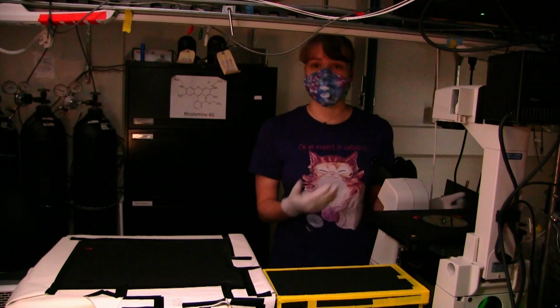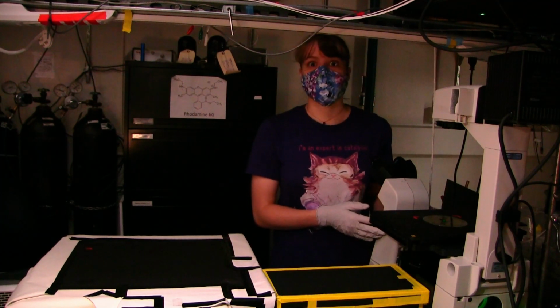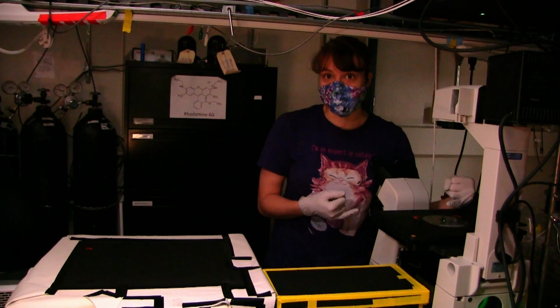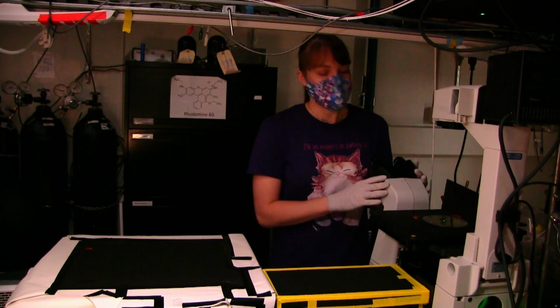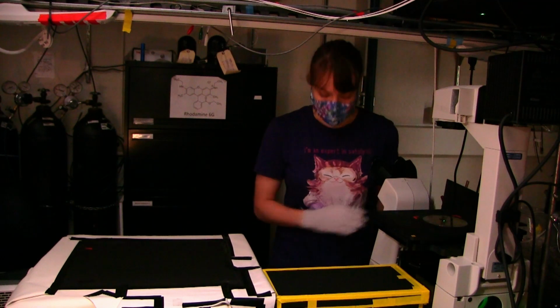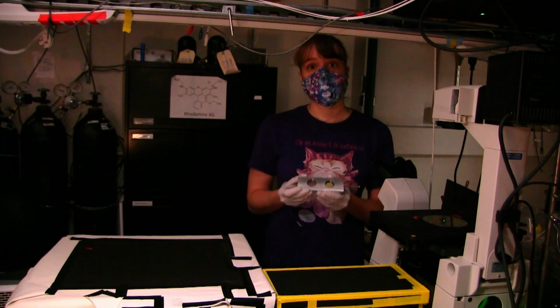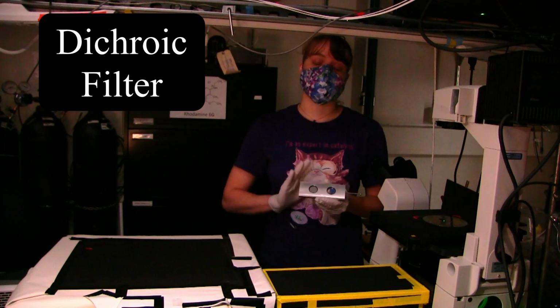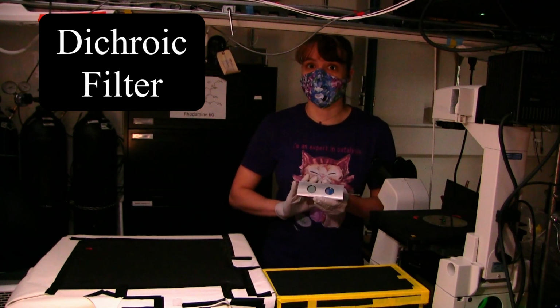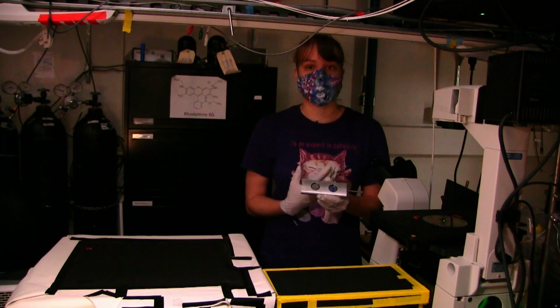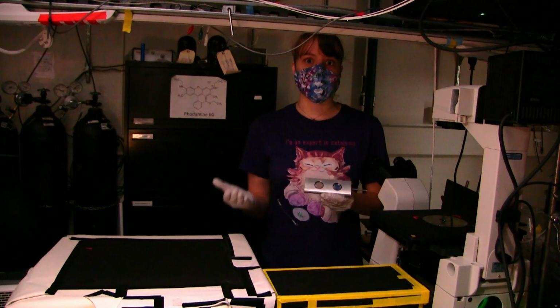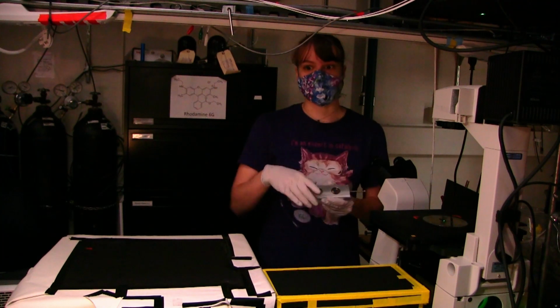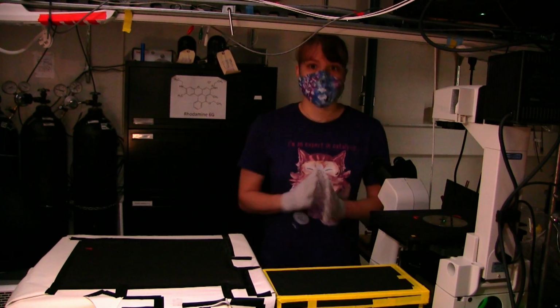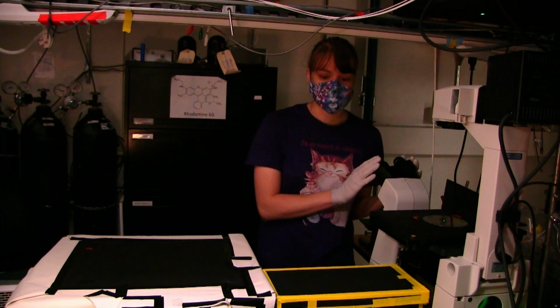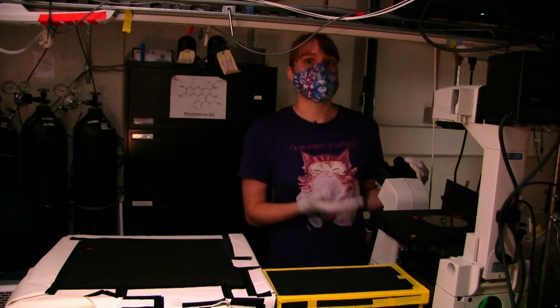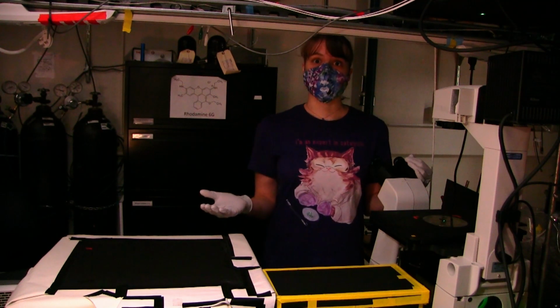In addition, there are a number of different optics inside the microscope that allow us to focus the beam onto our sample, so you can actually see the green light coming out of the objective, and other different manipulations we want to do to the light. For instance, this piece here is called dichroic. Now, dichroic is a fancy filter that blocks out specific colors of light. This allows us to look at our sample and only see the light coming from our sample instead of also seeing the green light from our laser. So, we can either look at our sample through the eyepiece, or we have a camera attached to this setup that allows us to take videos. We're going to show you one of these videos now.